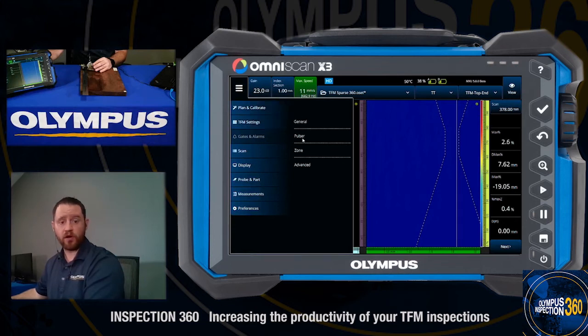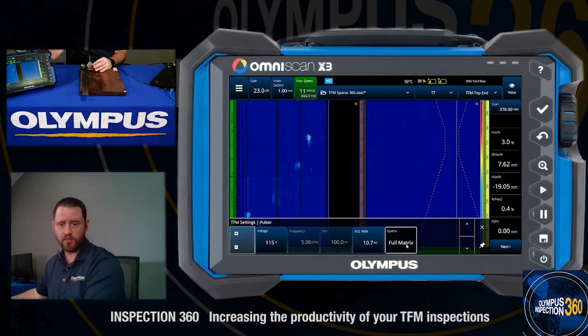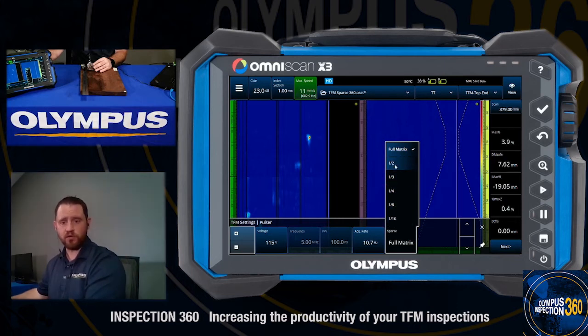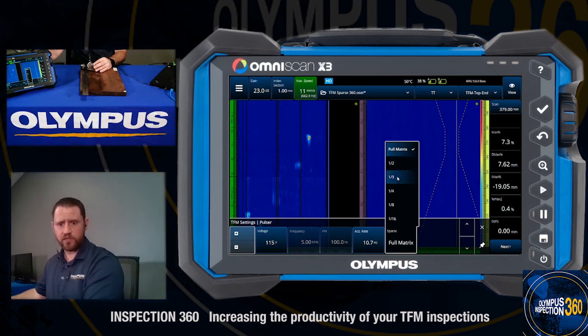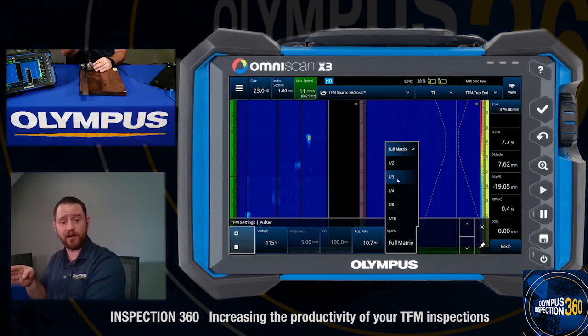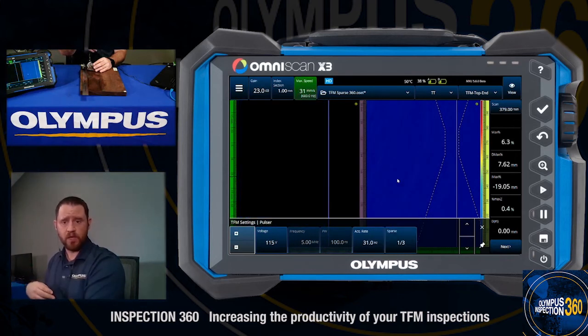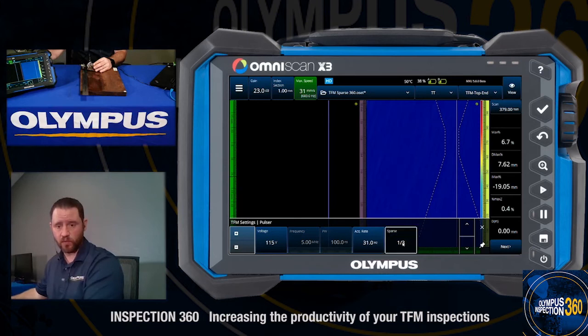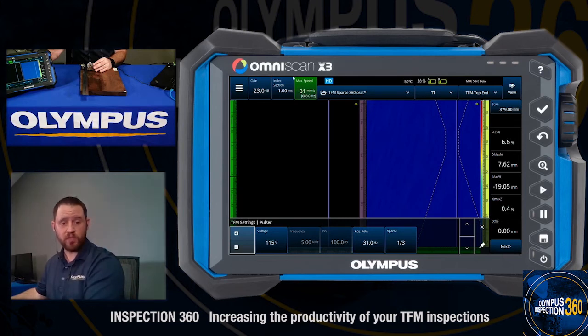Now we'll activate the sparse setting and compare and contrast what that looks like. In our TFM settings, under our pulser configuration, is where we find our sparse mode. Right now it's running full matrix, but we do have the flexibility to apply different levels of sparse firing: 1x2, 1x3, 1x4, 8, and 16. Going back to what we talked about earlier, this will skip whatever number of elements you see in the selection. So if we set this to 1x3, it means it'll skip two elements and fire every third element of the transducer. As soon as it finishes adjusting to the 1x3 sparse, we get a significant increase in our acquisition rate — now rather than collecting at 11 millimeters per second, we are collecting at 31 millimeters per second, which is a significant jump.